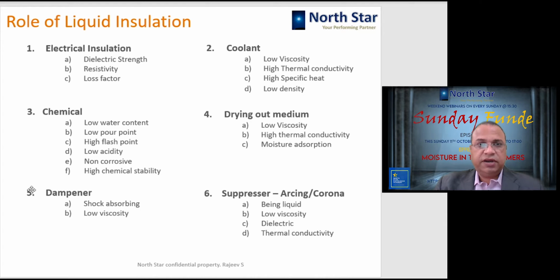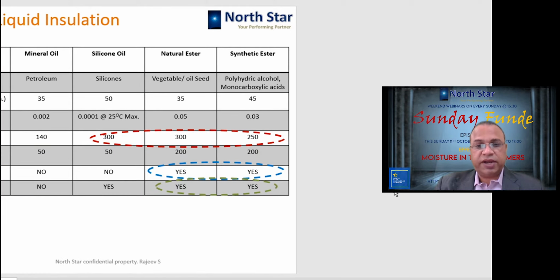Then it is a dampener. It provides a shock absorbing effect to the coils and solid insulation of the transformer winding, because of its low viscosity and being a liquid. And last is its arc quenching property. Because of that, it helps in extinguishing the arcs which happen inside the transformer, maybe because of operation of the OLTCs inside the transformer or any other reason. So it acts as an arc or corona quenching mechanism.